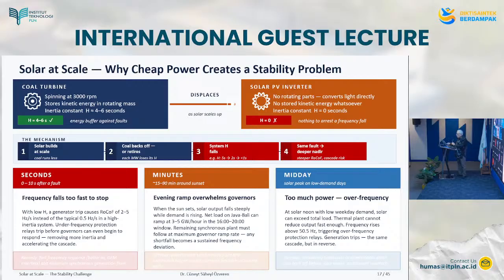Remaining synchronous, so I think for Java Bali, from what I've found out, between the 4 o'clock and 8 o'clock window, net load is ramping at 3 to 5 gigawatts per hour. And remaining synchronous plant must follow at maximum governor ramp rate. Any shortfall becomes a sustained frequency deviation. So if you can't match the load with your generation, the frequency will go down. So this is the 15 to 90 minutes around sunset. There's got to be some good dispatching going on.